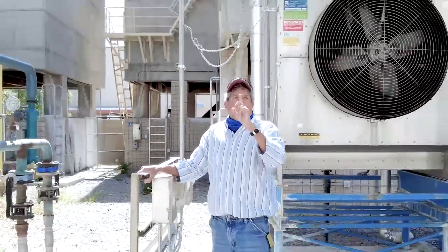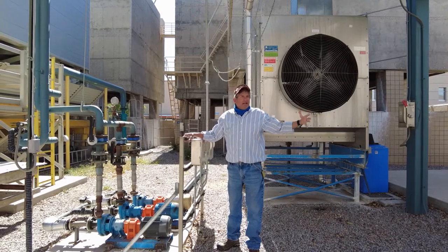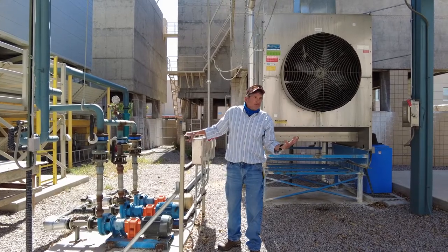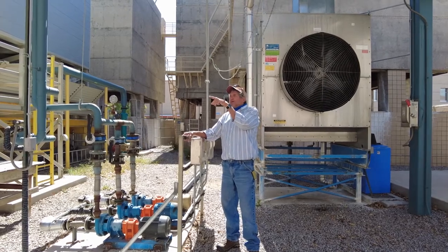Holy cow, what is going on? So I come hauling over here. Sure enough, we've got one phase feeding the core part of campus. What is happening? So we shut everything off, feed everything with El Paso Electric through campus. We start investigating.